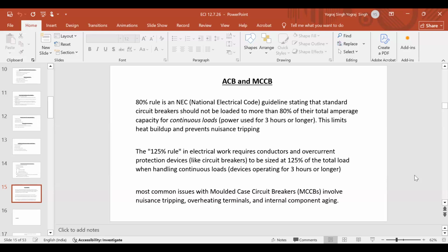Now next is the 80% rule and 125% rule. If I have a transformer of 500 kVA, the total load on it will never exceed 400 kVA. Suppose it will bear 500 kVA also, but if it is more than 3 hours or longer, slowly heat will be there. Yes, anybody wanted to know anything?